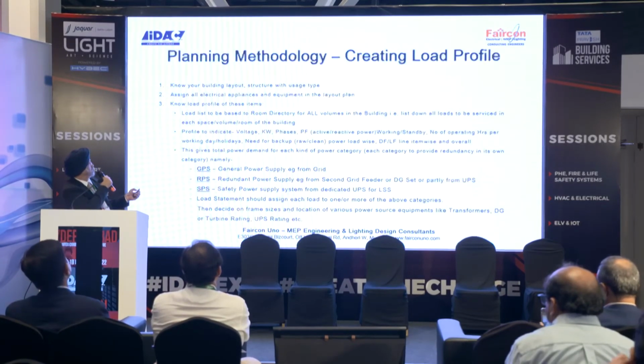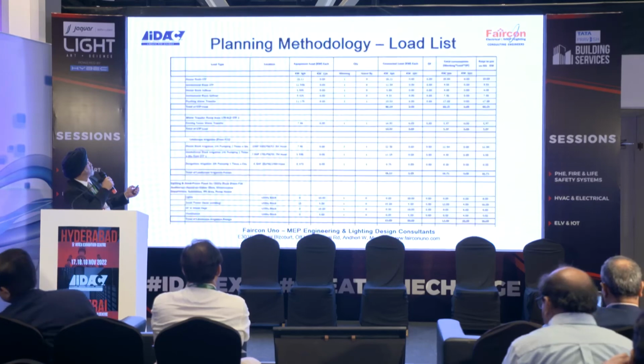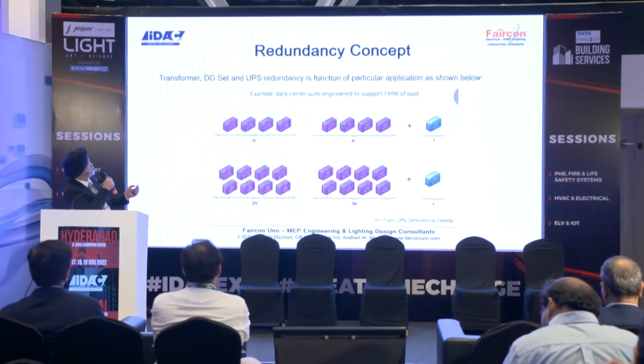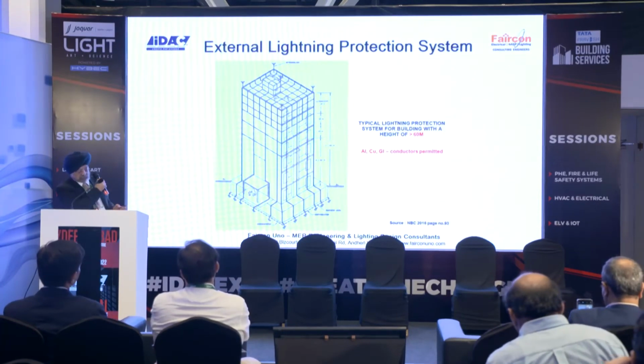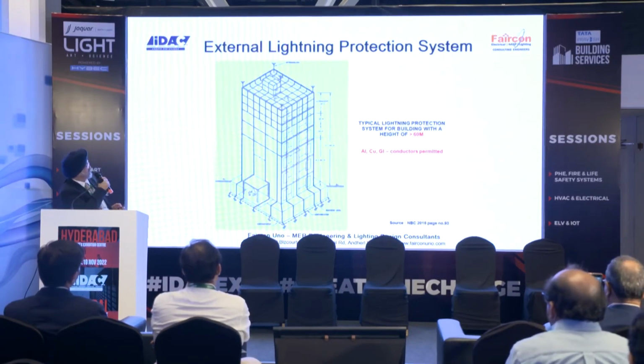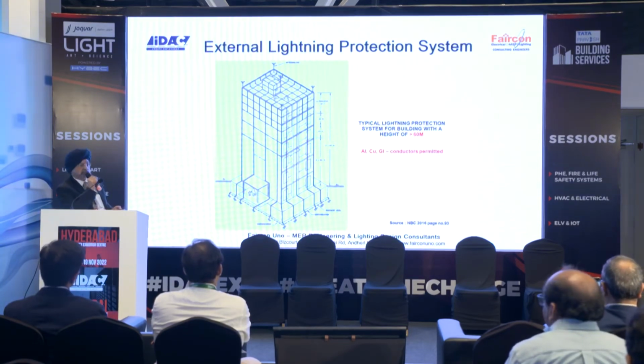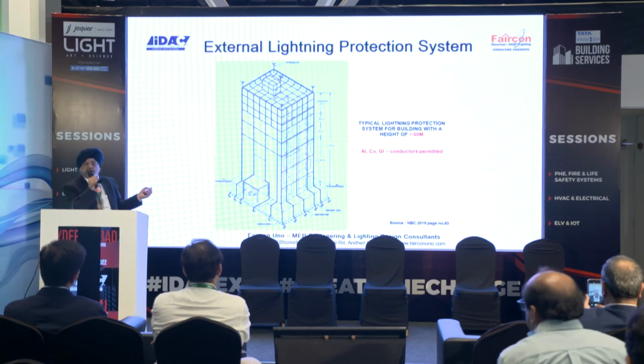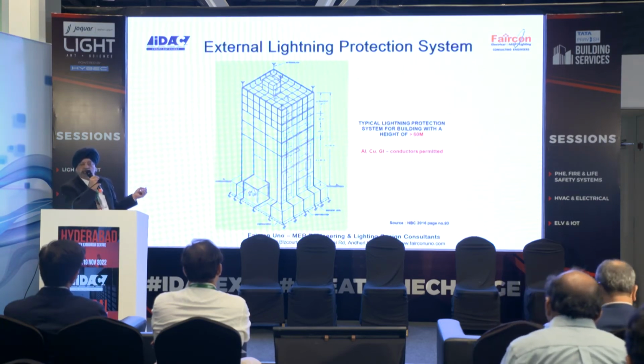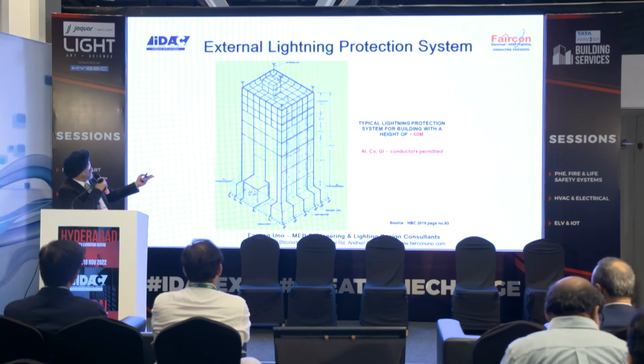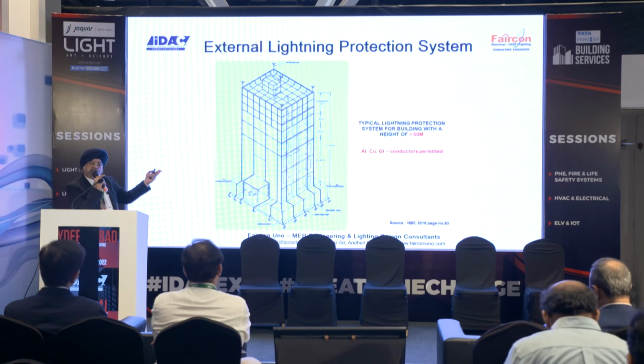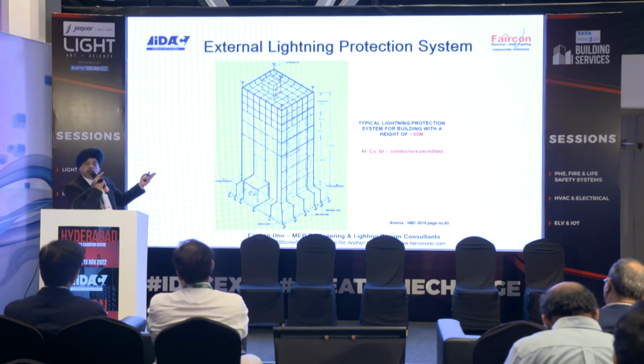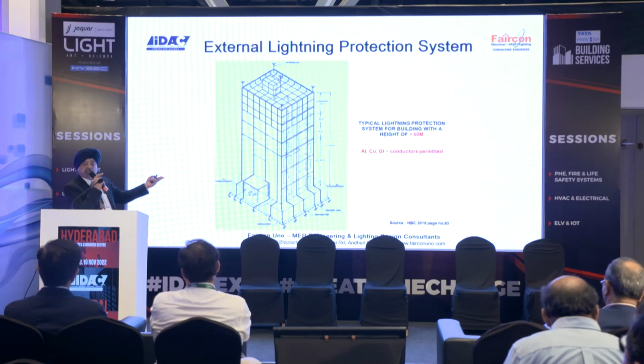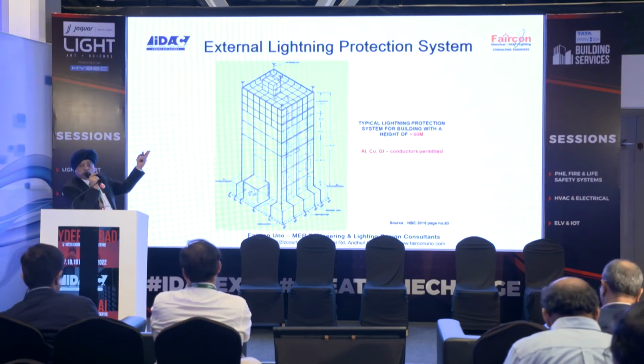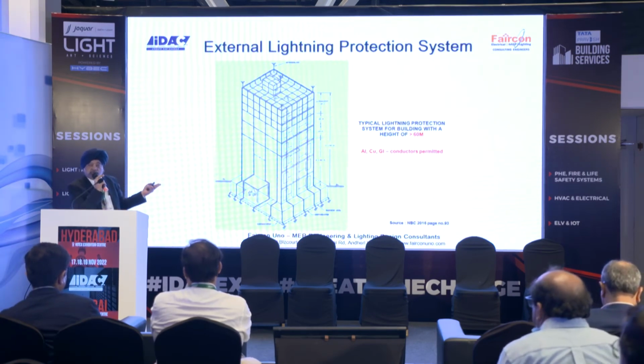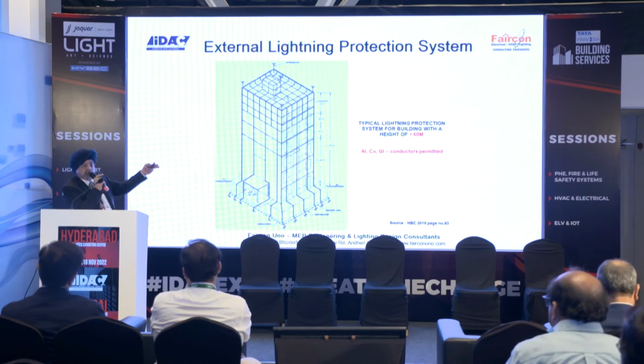Now, see, lightning protection is basically a Faraday cage, and there are manufacturers who give you factory-built systems like OBO and DEHN, who will also guide you on what the ring around the building should be, horizontal. These buildings need aviation lights on top as well as on the sides. Similarly, a lightning protection ring along the building is required.